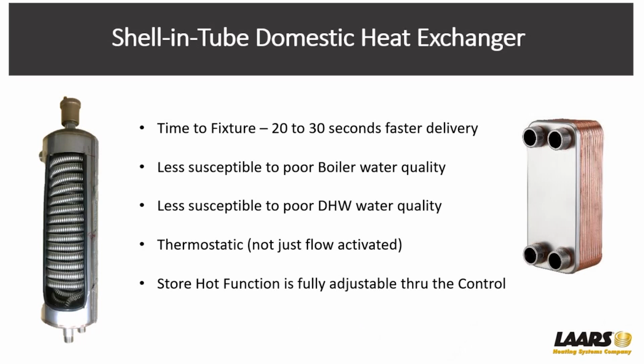Now, I also want to talk a little more about the shell and tube design heat exchanger. We list this as time to fixtures, 20 to 30 seconds faster than a plate type. So a lot of manufacturers are using the plate type heat exchangers for domestic. And what happens here, example of that, you turn on a faucet or a shower valve, and the boiler has to have some type of flow switch or a flow device telling you that it's in domestic mode. So with a flow switch, it triggers it, tells the boiler that we need a domestic demand. Well, we don't light right away. You have to modulate up. It's called pre-purge. And most manufacturers are going to modulate to 80 or 100%.